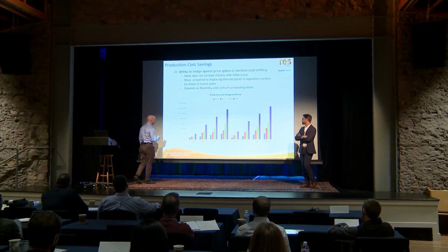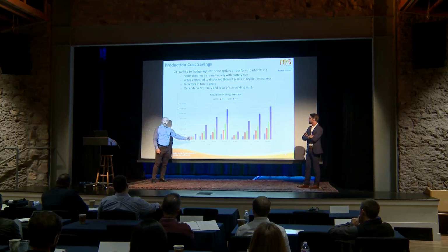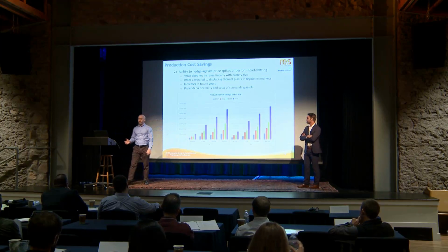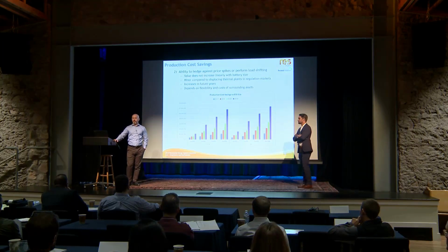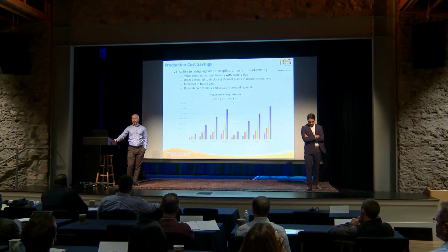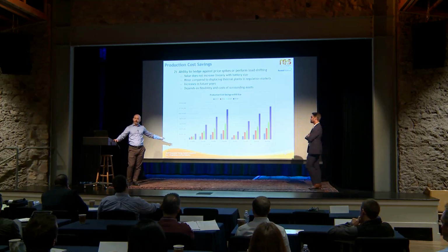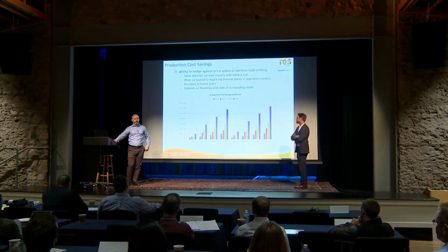The 10 megawatt battery was able to cover all of the worst regulation choices. When we desperately needed 10 more megawatts of regulation, we had to start up a CT to do it, or run a coal plant at some level we would hate to. The 10 megawatt battery covered all those really bad cases that crop up over the year right off.